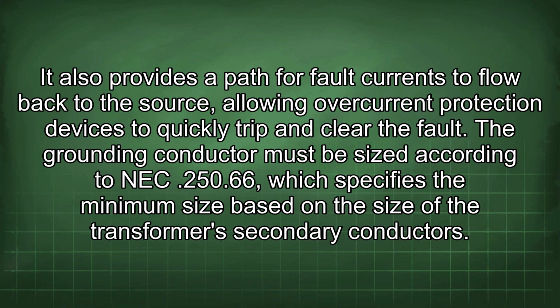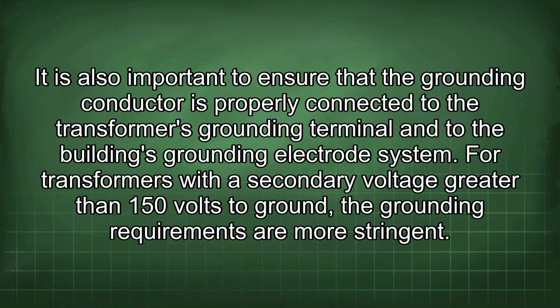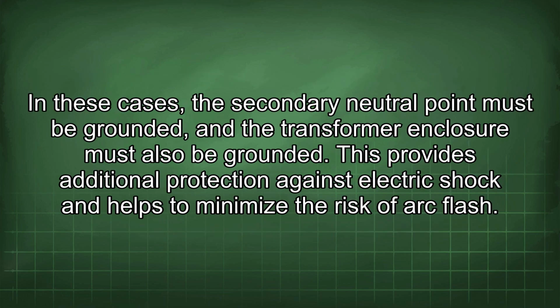It also provides a path for fault currents to flow back to the source, allowing overcurrent protection devices to quickly trip and clear the fault. The grounding conductor must be sized according to NEC 250.66, which specifies the minimum size based on the size of the transformer's secondary conductors. It is also important to ensure that the grounding conductor is properly connected to the transformer's grounding terminal and to the building's grounding electrode system. For transformers with a secondary voltage greater than 150 volts to ground, the grounding requirements are more stringent. In these cases, the secondary neutral point must be grounded, and the transformer enclosure must also be grounded.